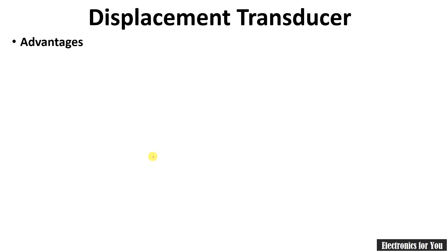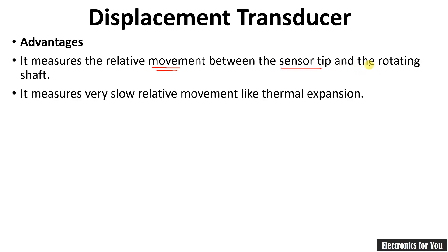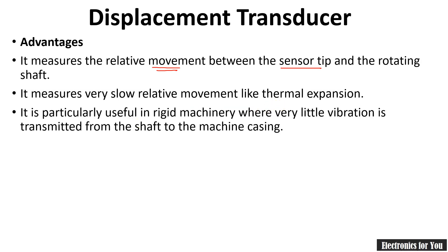The advantages of the displacement transducer: it measures the relative movement between the sensor tip and the rotating shaft. It measures very slow relative movement like thermal expansion. It is particularly useful in rigid machinery where little vibration is transmitted from the shaft to the machine casing.